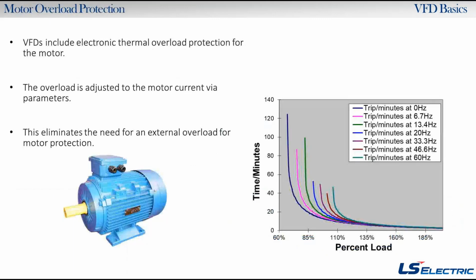Our next question is about overload protection. The nice thing is the drive has a built-in electronic thermal overload. So you go into your programming, and you program your motor voltage, then you program your motor amperage. And then the drive says, okay, you told me I'm a 13 amp motor. If I go over 13 amps, I'm only going to give you a certain amount of time to run at that high amperage before I trip you out. So there's no more need for an external overload. That's a little bit of a cost savings, and it's an adjustable overload via parameters.